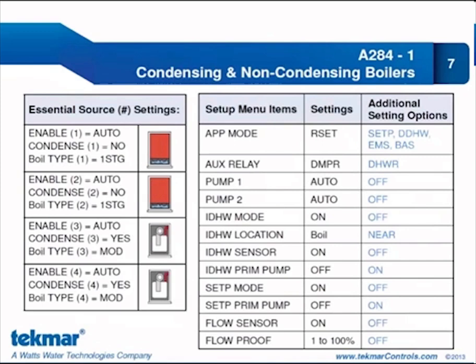They are enabled by selecting auto. This time, condensing is yes, and the boil type is mod for modulating. The rest of the essential settings are in the setup menu. The first one that comes up is the application mode. In this case, we are in the reset application mode to provide outdoor temperature reset water temperature for the space heating.